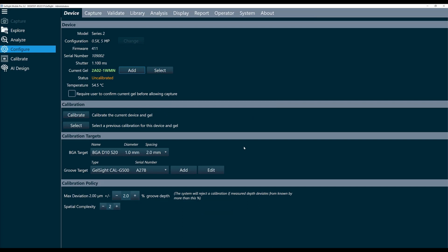Each gel needs to be calibrated before you can use it. Let's say you have 4 different gels. You can calibrate all 4 of them and then put them back in the box. And then when you need them, you can use the Select button to select from a list of existing calibrated gels. You don't need to calibrate the gel each time you connect it to the probe, just that one initial time before it can be used.